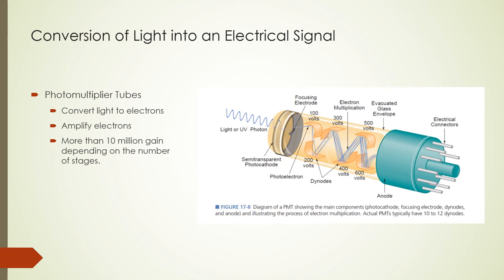Light produced by a scintillator is first amplified and converted to an electrical signal before it can be measured. This conversion is done by using a photomultiplier tube or photodiode. A photomultiplier tube has a semi-transparent photocathode that converts light to electrons. The electrons are accelerated by application of high voltages between electrodes called dynodes, and the accelerated electrons are focused on an anode. The photocathode, dynodes, and anode are in a vacuum enclosure. A photomultiplier tube has 10 to 12 dynodes and provides amplification factors of more than 10 million.